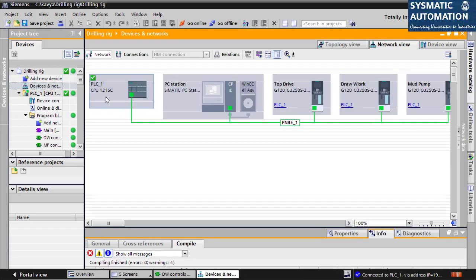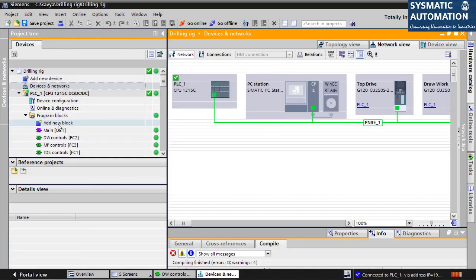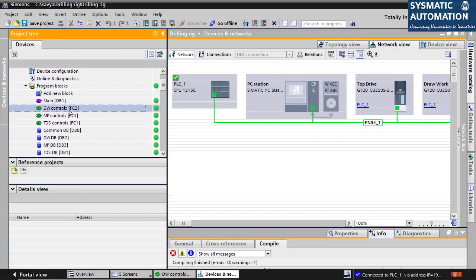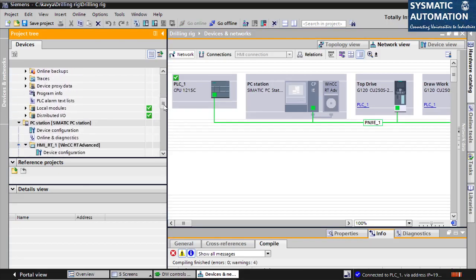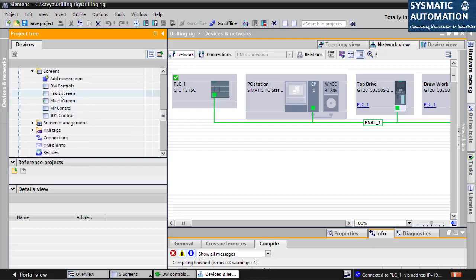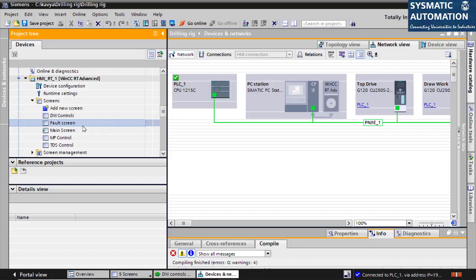See, this is the PLC one, which is the master PLC, which will communicate to my top drive VFD, drawworks VFD, and mud pump VFD. And instead of HMI, I'm using a SCADA system here. So the same PLC will send all the signals to the SCADA. From the SCADA, it goes to each of the VFDs of top drive, drawworks, and mud pumps. In the programming section, we have written a program for the control of drawworks, mud pump, and top drive. Similarly, in the SCADA, we have designed four screens: one is the main screen, then the drawworks control, mud pump control, top drive control, and there's one fault screen.